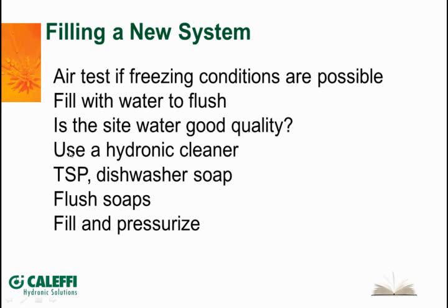It's good for your pump seals. It's good for all your piping and all your heat exchange surfaces, because in addition to cleaning out the chemicals or the dirt and debris in there, they put a little bit of a film provider in there, so they coat the inside of your pipe and heat exchangers. I've heard guys say they use TSP, especially on steam boilers, because it leaves your water a little alkaline, which is good for a steam boiler. Dishwasher soap. Really, hydronic cleaner is the best thing to use because it's formulated just for that application, and it's got the film providers and other things in it.